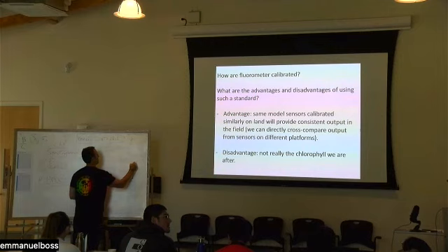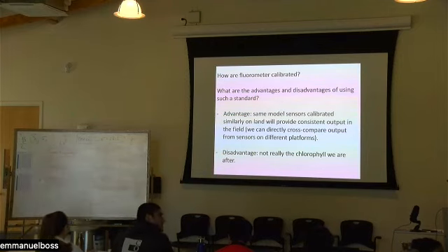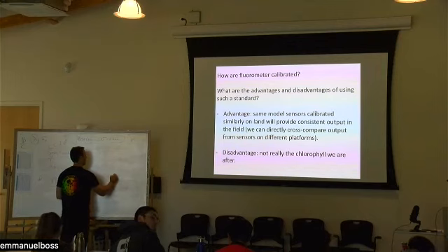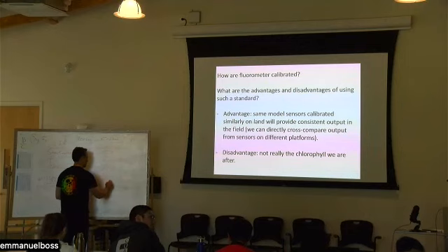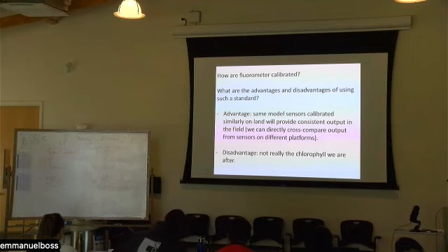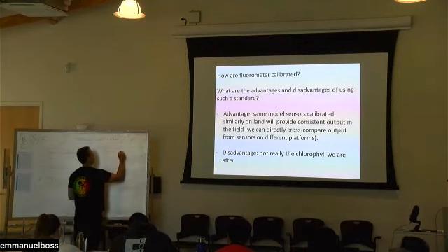And it depends on your solvent. And so even if you could put your fluorometer into a solvent to measure it, which I would recommend not to do, it has some epoxies on it, you will just dissolve your instrument. It's not going to excite chlorophyll. So you literally can't use a purified chlorophyll standard for your in situ fluorometer. So just make sure that you're very, very clear on that.